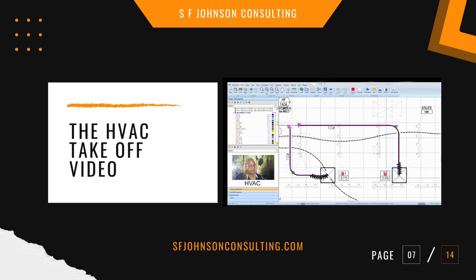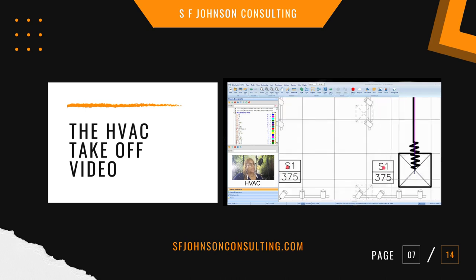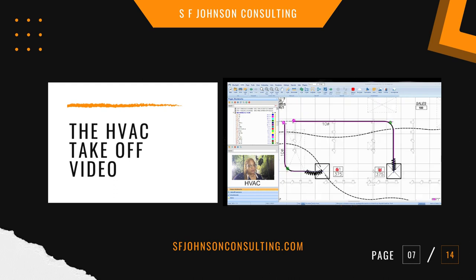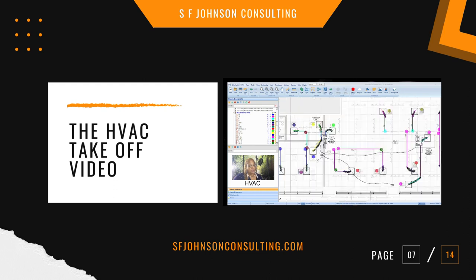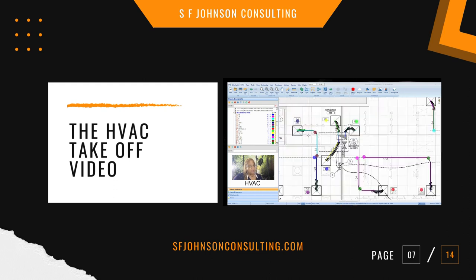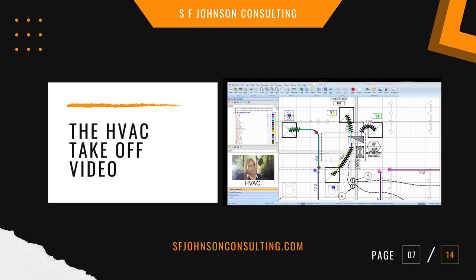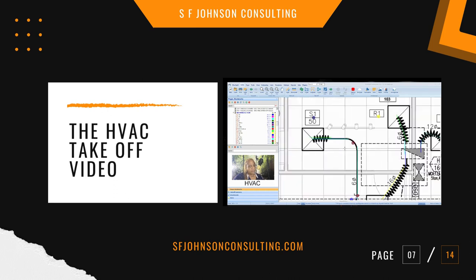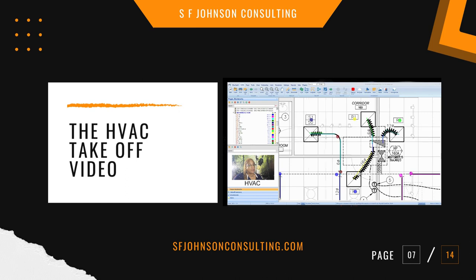X is supply grill. And this number indicates CFMs, right? The amount of cubic feet of air through the supply grill per minute. And so that's what you'll always see there. So just account for the 90s. Make sure you have, this is a 6-inch spiral, so make sure you account for the 6-inch neck size. Because again, the prices of the supply grills are going to differ based on the neck size.